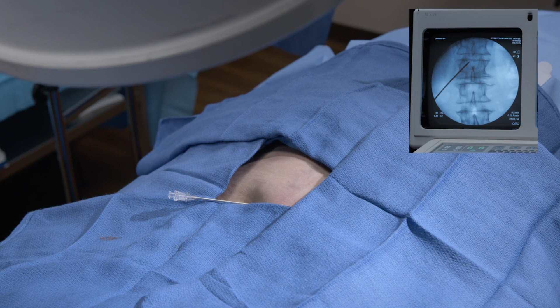Now, the sheath that we use most of the time is this heavily curved sheath. There's actually a gentler curve as well, but the heavier curved sheath makes it a lot easier for many of the areas that you're going to apply. Now, there's a little hub at the end there, and that hub is so that you can adjust where it's going, and then you're going to lock the lead into place there. So anytime you're going to adjust the lead or advance it, you're going to have to unlock it.